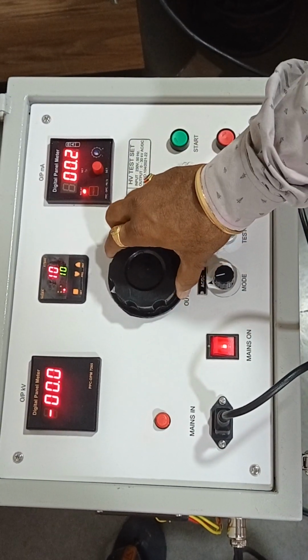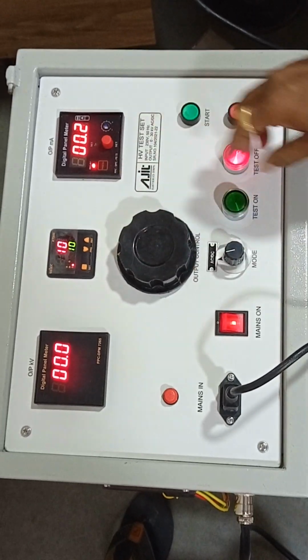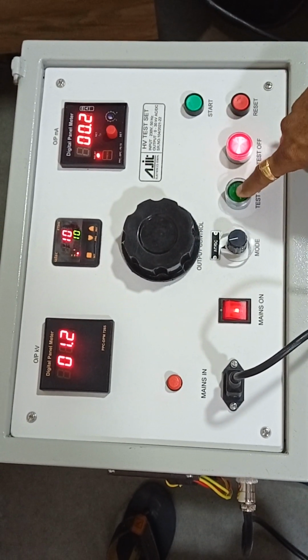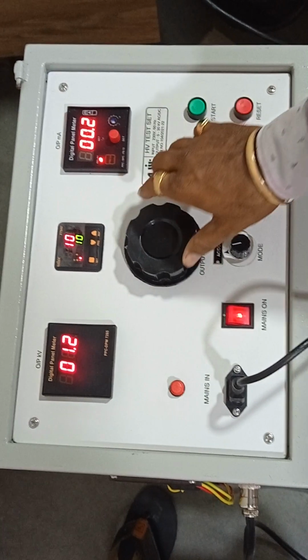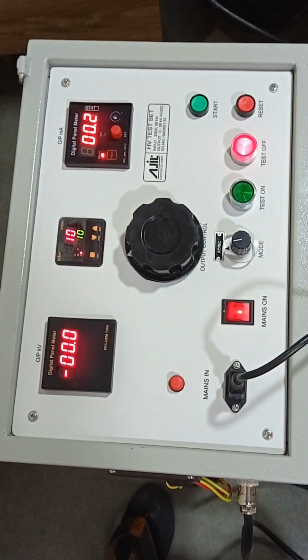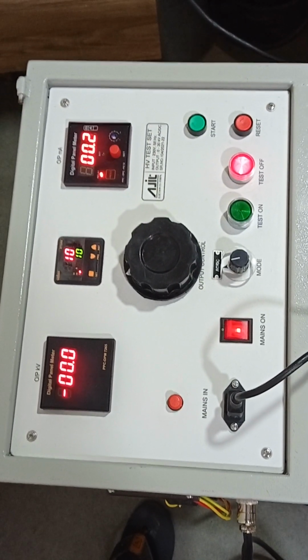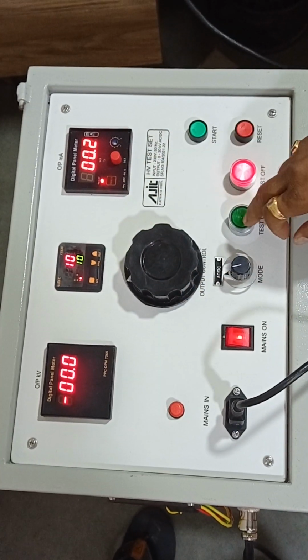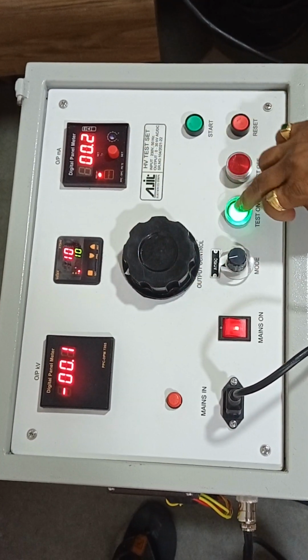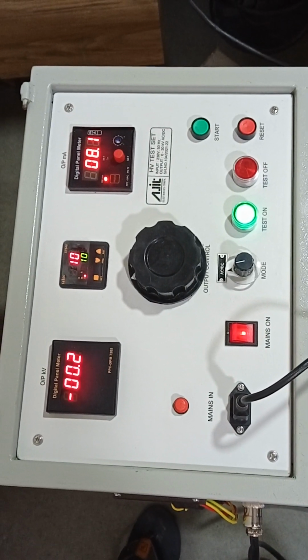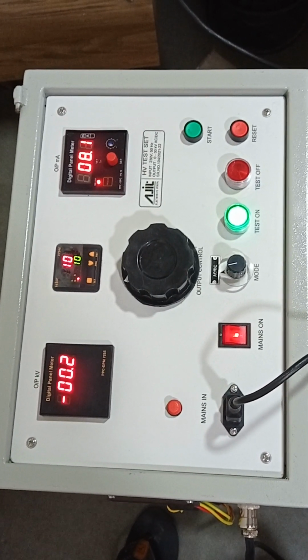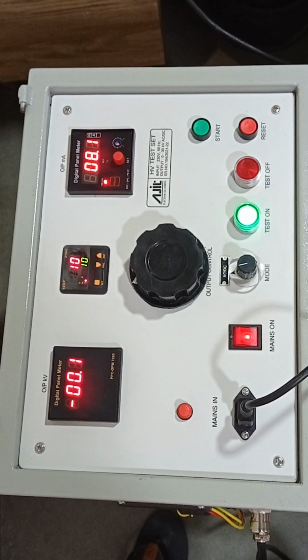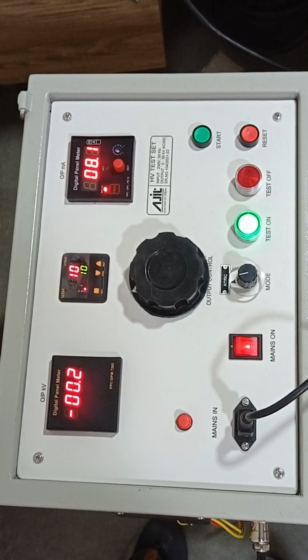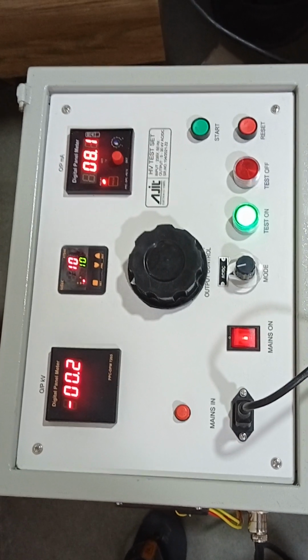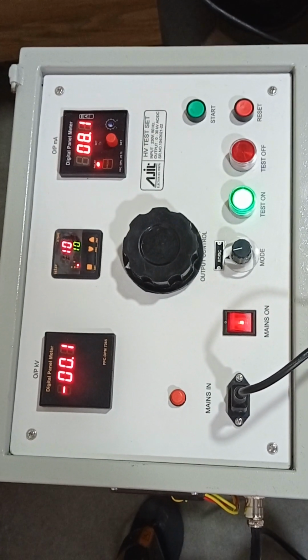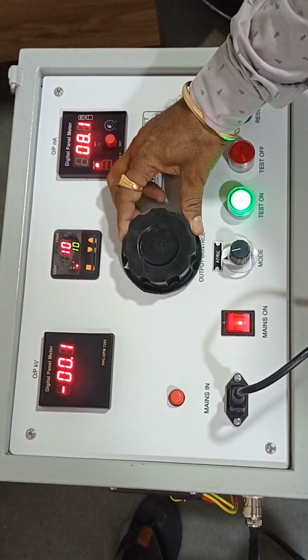Now check the zero. If we are not at zero, the instrument will not start. This is one of the interlocks provided, called the zero start interlock. Now I am at zero, and now I can start the HV. Now the HV is started. The leakage current through the high voltage to ground is flowing, and it is 8.1 milliampere. If I cross 9.5, which is set, the instrument will trip for overcurrent.